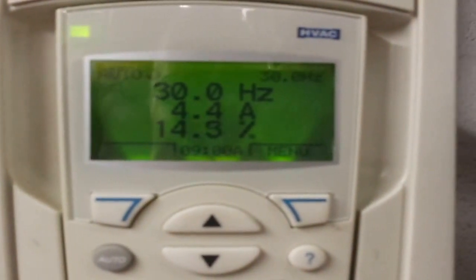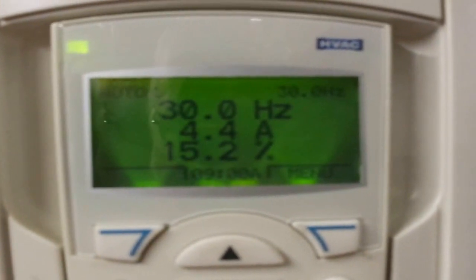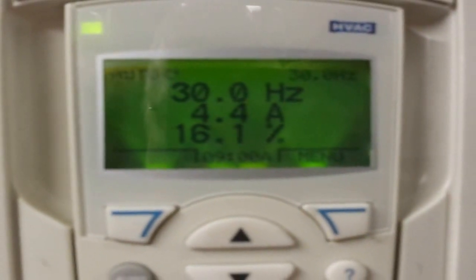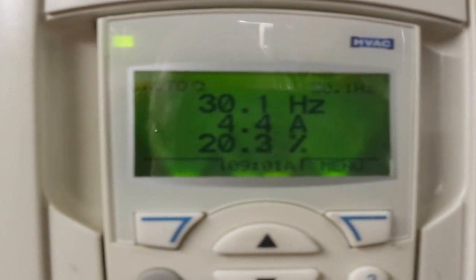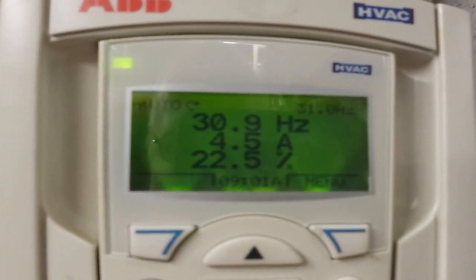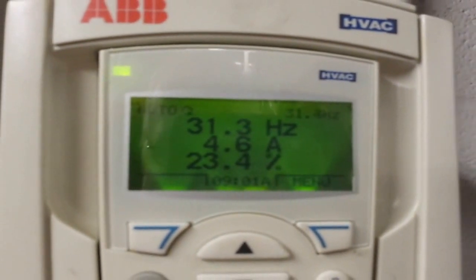You can see that we just went to 10 percent on the output from the controller, and that coincides with what we are seeing on the drive. However, you also see that the drive is still putting out a consistent 30 Hz. The reason for this is the percentage of the input signal for the speed reference has not exceeded the 30 Hz threshold — in other words, we do not have a command to the drive to run the motor more than its minimum. If that set point exceeds the frequency threshold, then we will see an increase, which we are starting to do now. We are at 21.9 percent, 22 percent, and you can see that it is actually starting to increase the frequency output from the drive.